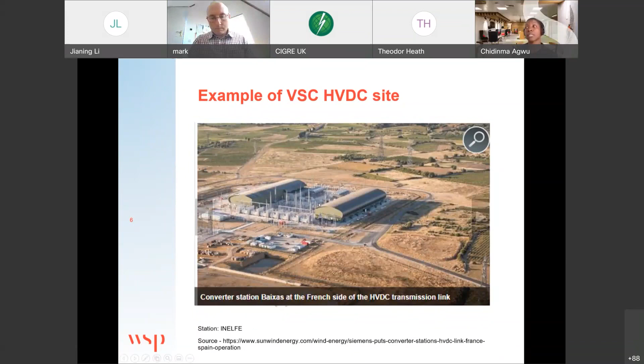One of the things that you can see straight away is just the size. You can see here you've got your building, which is your converter building. It's got your IGBT stacks in there. So that's one pole, that's your other. You've got your transformers at the base there, but the really massive difference is that with VSC, and with this particular project, you do not need your harmonic filters. So the space requirement that you had for these filters is just not the same for a VSC plant, which also means that the equipment that you have is less, and therefore the equipment that is generating noise is a lot less.